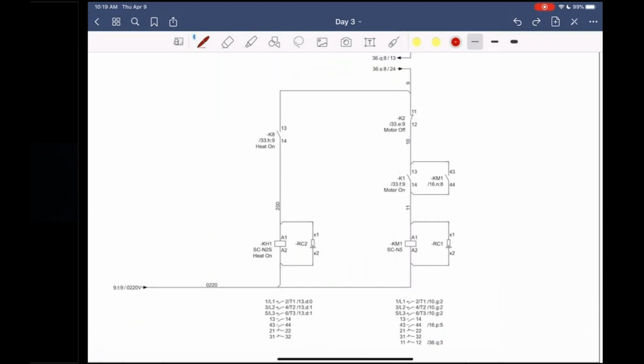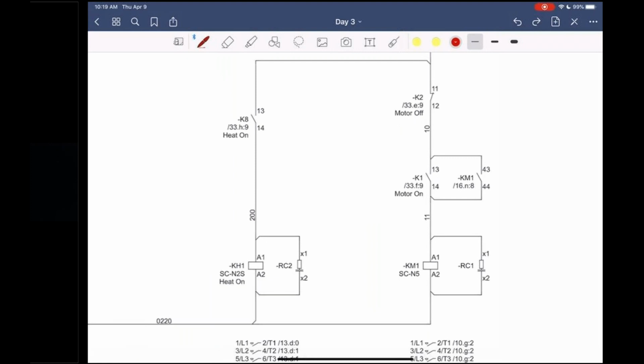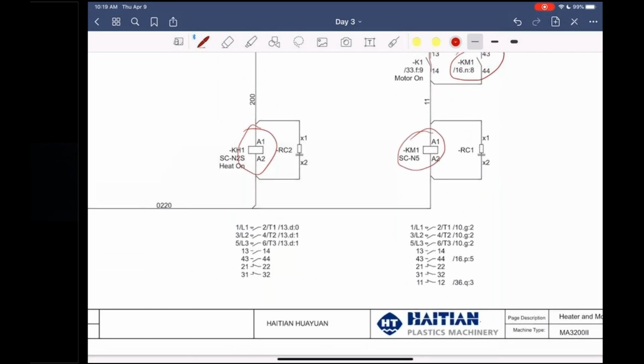This is the heater and motor start circuit. So when you turn motor on, it energizes K1, which then activates this contactor, which will close this set of contacts. And that'll turn the drives, energize the drive power. When you do the same for the heater on, it'll energize KH1, which will then keep the heats on. To find out where these solenoids are attached to the contacts, it's right here at the bottom. And KM1 controls these set of contacts. Questions so far?